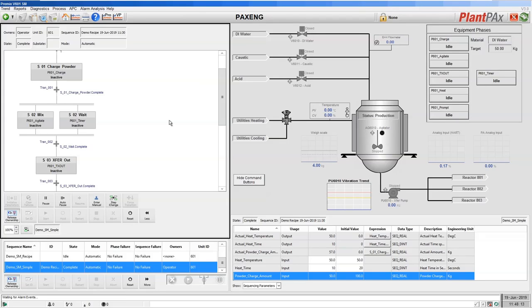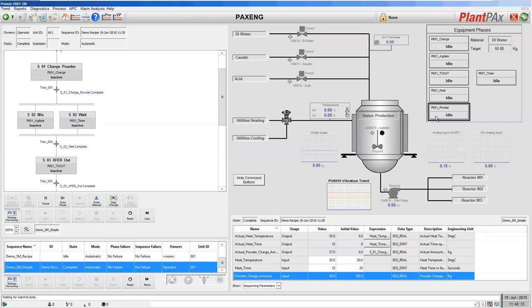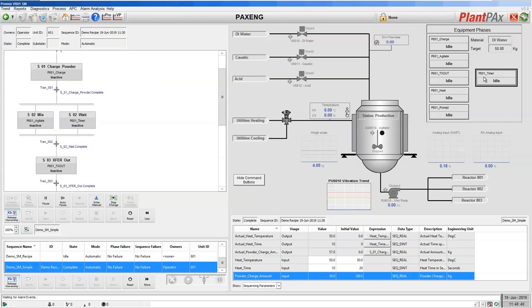Similarly, I've decided that I need an equipment phase to do agitation, so that will control the agitator for our tank. Again, I need a phase to be able to transfer out the material to the next reactor, a transfer out phase. I need an equipment phase to control the temperature in the reactor, so a heating phase. I wish to have an equipment phase that prompts the operator with simple messages and asks them to confirm and give a response when they've done it. And I need a phase to do timing, so I can time for periods of time.